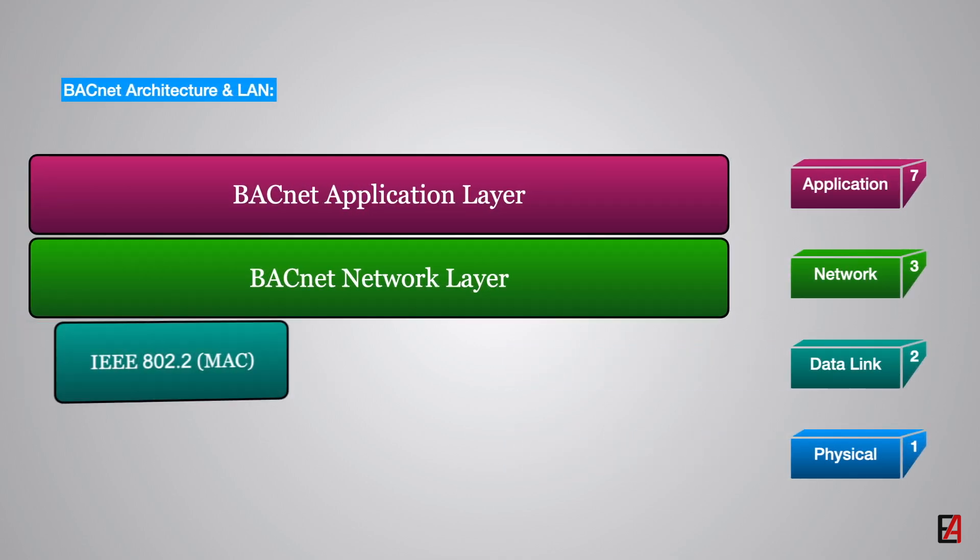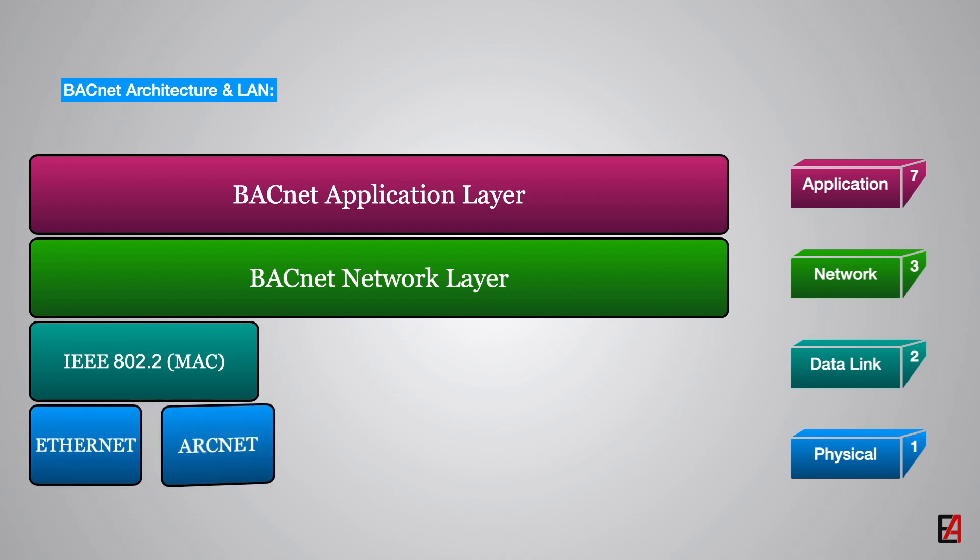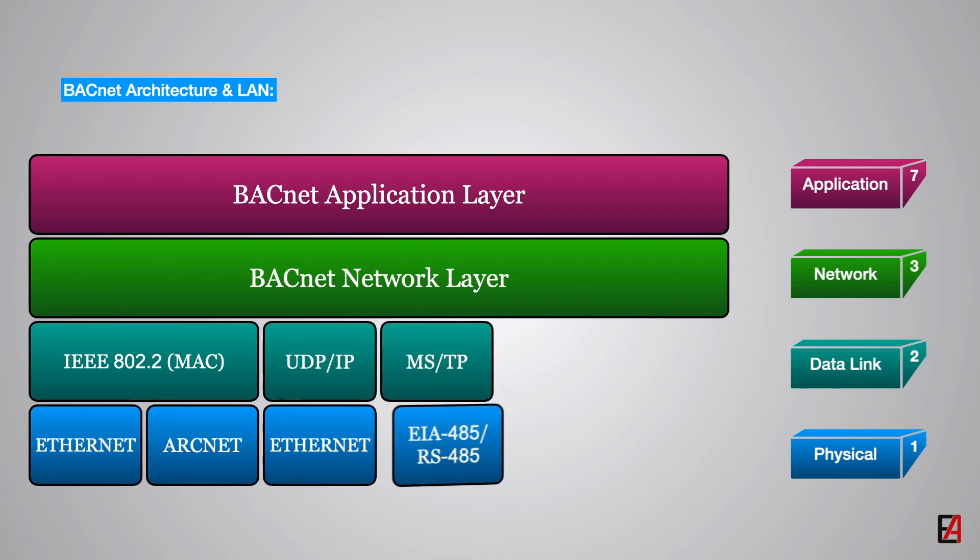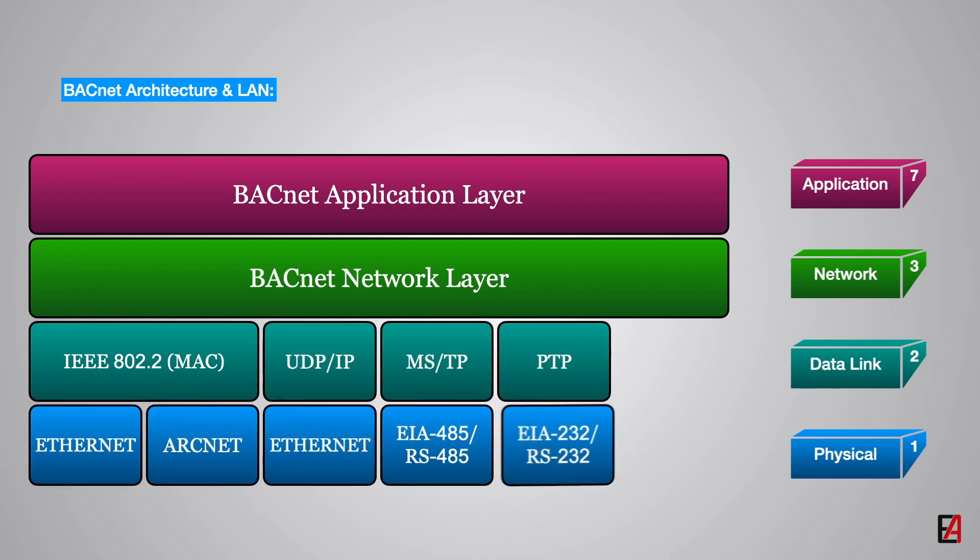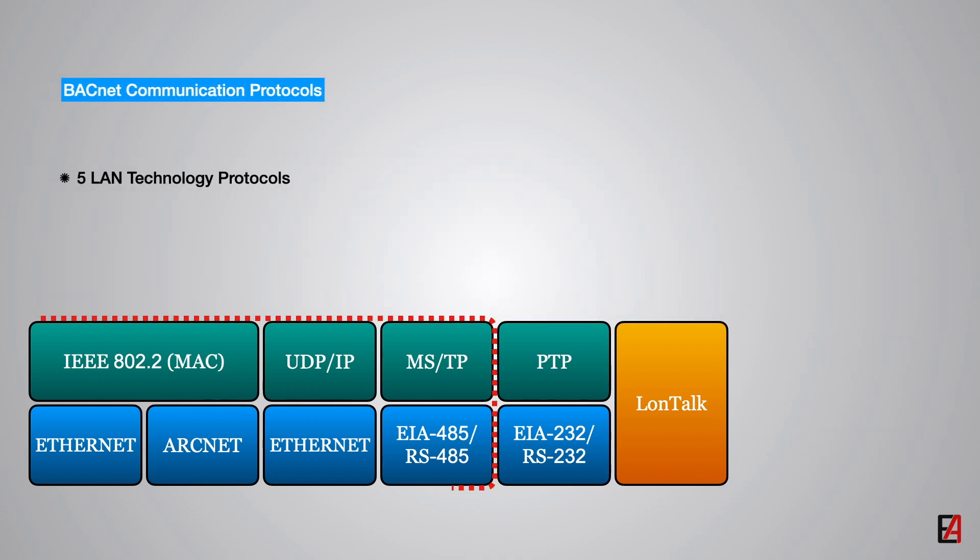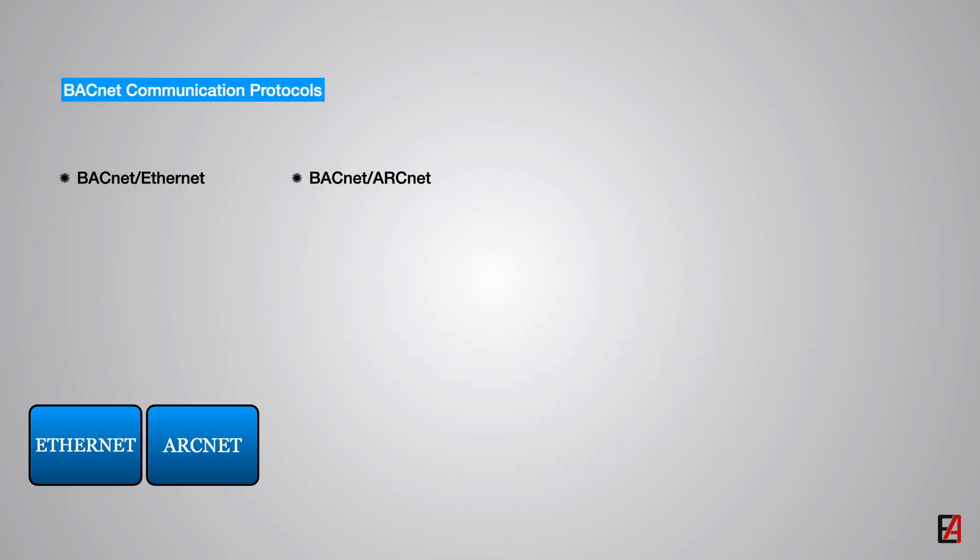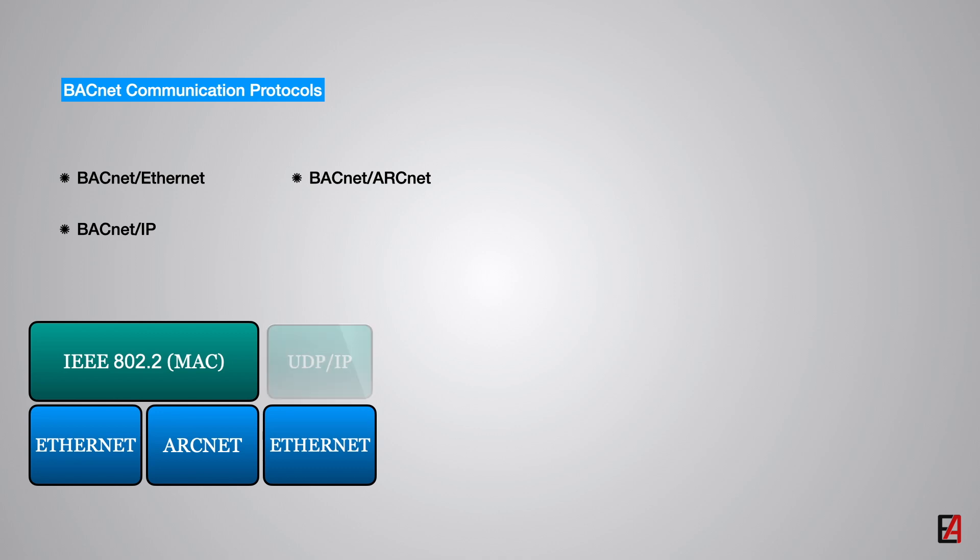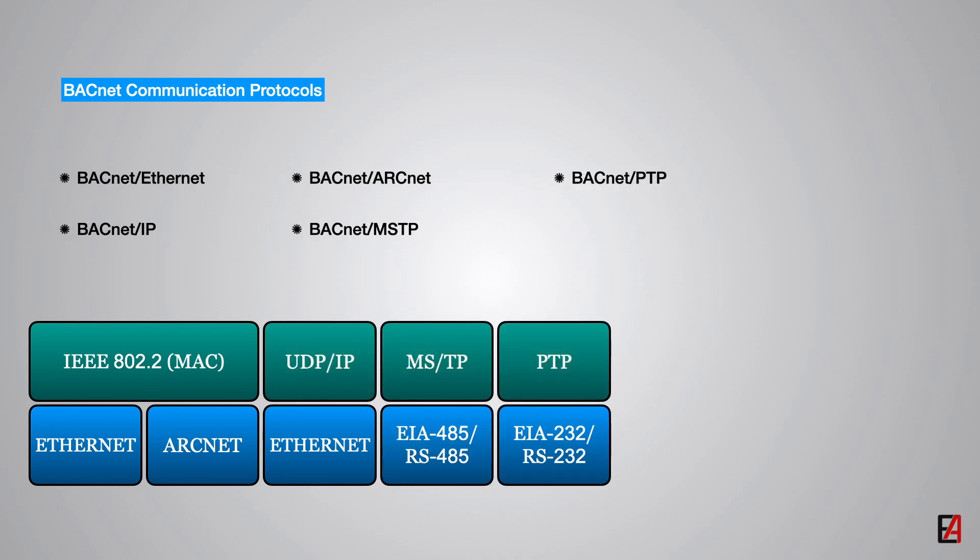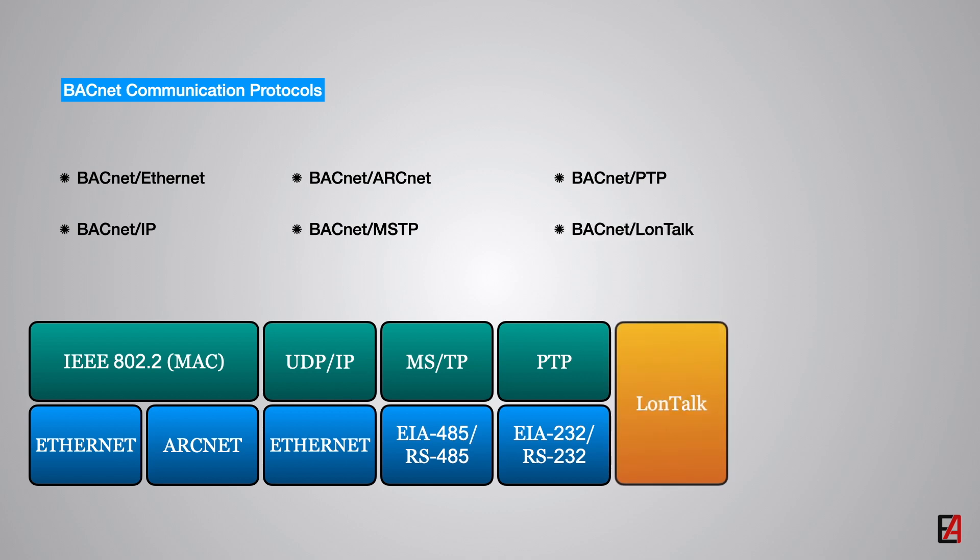The physical and the data link layers represent the LAN technology options supported by the BACnet. As seen in this architecture, BACnet provides five LAN technology options: BACnet Ethernet, BACnet ARCNET, BACnet IP, BACnet MSTP, BACnet LonTalk and one point to point protocol BACnet PTP.